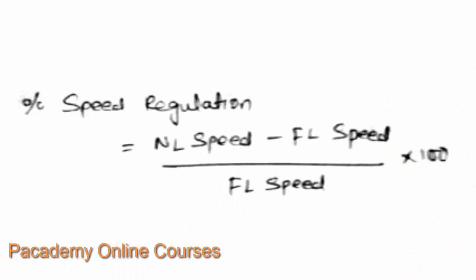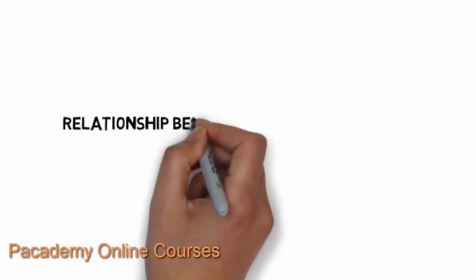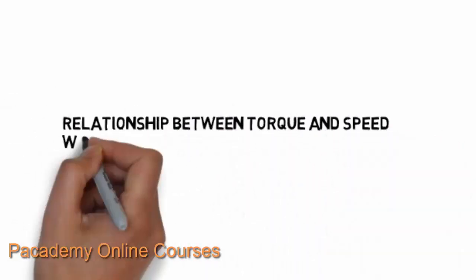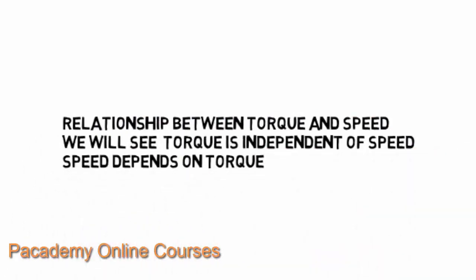Speed regulation of an electric motor is defined as the ratio of (no-load speed minus full-load speed) divided by the full-load speed, multiplied by 100. It describes how much the speed reduces from no load to full load — in other words, if the load is suddenly removed from the motor, how much the speed will vary.